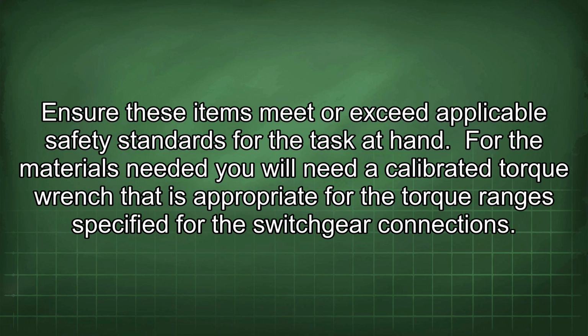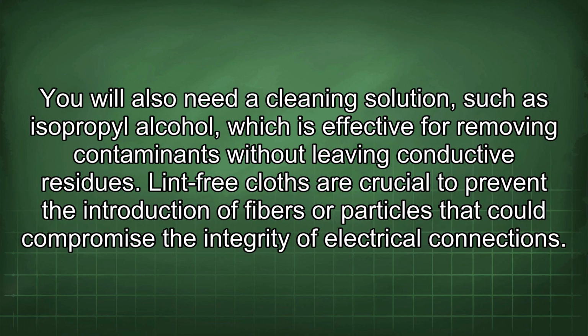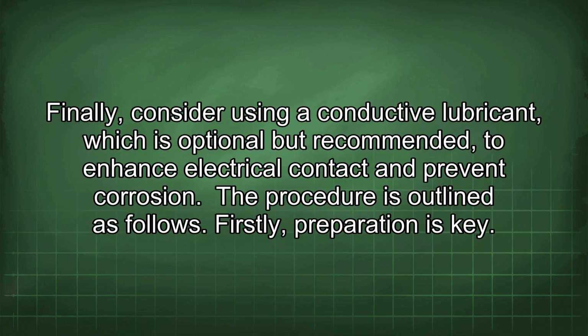For the materials needed, you will need a calibrated torque wrench that is appropriate for the torque ranges specified for the switchgear connections. You will also need a cleaning solution such as isopropyl alcohol, which is effective for removing contaminants without leaving conductive residues. Lint-free cloths are crucial to prevent the introduction of fibers or particles that could compromise the integrity of electrical connections. Finally, consider using a conductive lubricant, which is optional but recommended to enhance electrical contact and prevent corrosion. The procedure is outlined as follows.